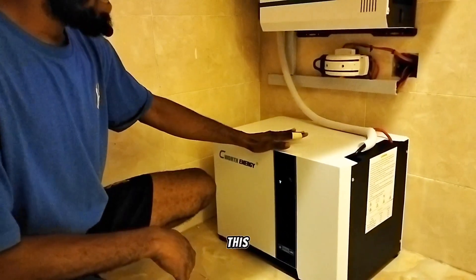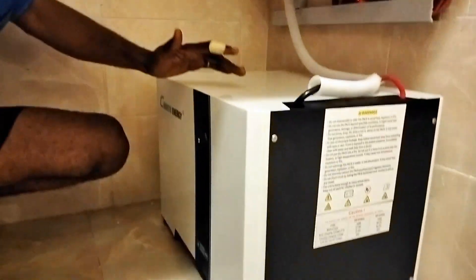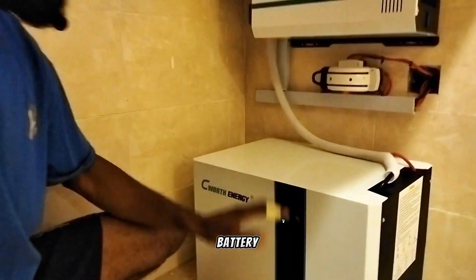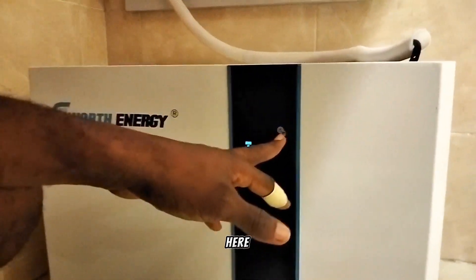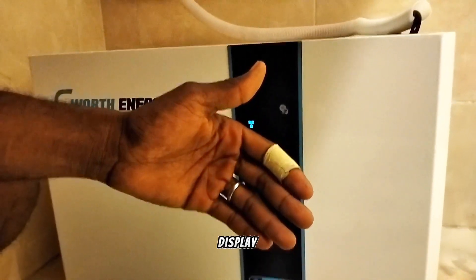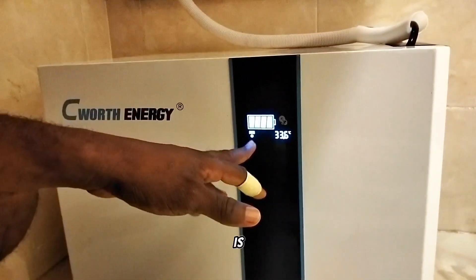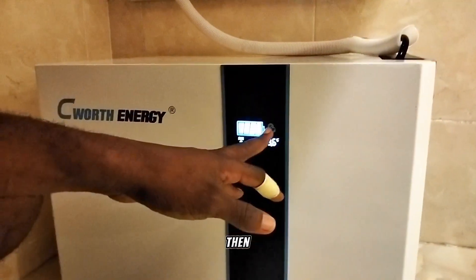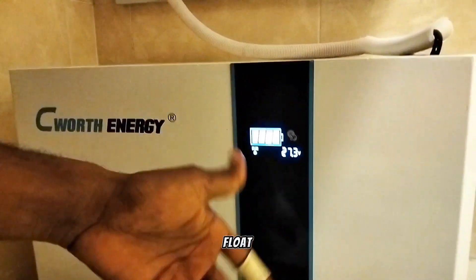This is a Cworth Energy LiFePO4 battery and it is 5 kilowatts — equivalent to about two 200Ah tubular or gel batteries. It has a screen and a soft-touch display. Right now the screen is not showing, which means the battery is on and everything is working fine. If you touch it, it will display the battery voltage, battery bar, and battery temperature. Let's touch it — you can see it's showing the battery is full from the battery bar, and the temperature is 33.6 degrees Celsius.